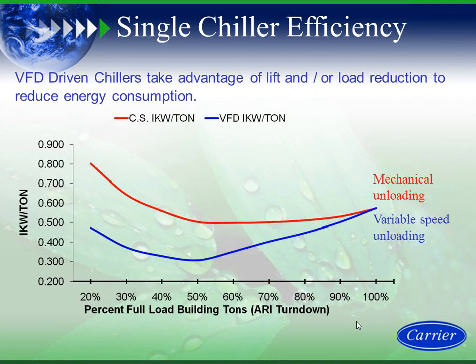When we look at this, as the building load drops, which is the lower axis, my condenser water temperature gets colder. As I get colder condenser water temperatures, my machine gets more efficient. So when I'm at approximately 50% load on the building, 50% load outside, I'm running at pretty good kW per ton with cold condenser water. Whereas with a mechanical unloading device, you are going to get some energy savings with cold water. However, it's not going to be as significant because I'm not reducing the RPM of the VFD motor.